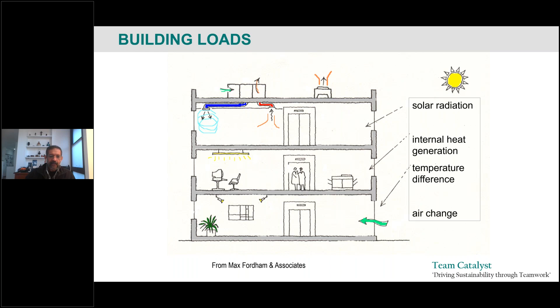In Australia, for example, in our National Construction Code, the lighting component of energy cannot be more than 4.5 watts per meter squared for an office building. Now that's quite an efficient lighting system, so there's very little heat being provided by that system, but it is still there - it needs to be counted in the model.